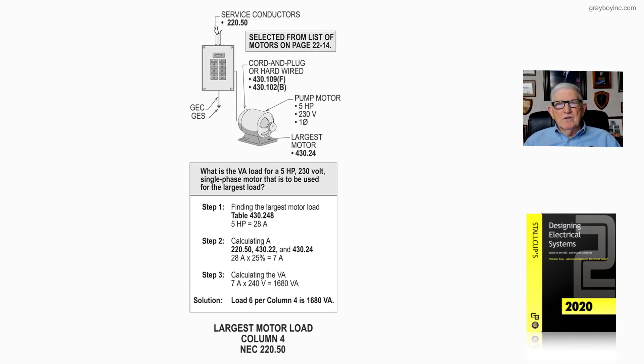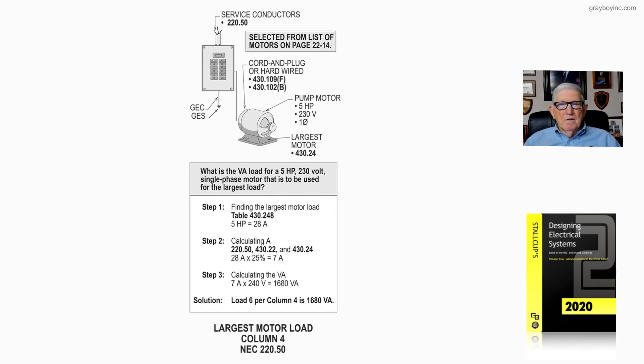We can select from the list of motors on page 22-14 of Stallcup's Electrical Design Book, or Designing Electrical Systems, Volume 2. Notice cord-and-plug connected or hardwired — 430.109(F) gives you your rating and disconnect location, and 430.102(B) gives the exact location. The pump motor is a 5 horsepower, 230V, single phase.